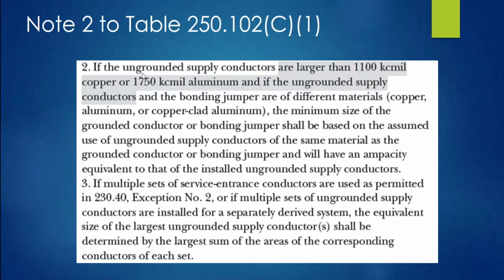Okay, again, if the ungrounded supply conductors are larger than 1100 and 1750, and if the ungrounded supply conductors and the bonding jumper are two different materials, in other words, the aluminum conductor's coming in and the bonding jumper is copper, the minimum size of the grounded conductor or the bonding jumper, now we're talking about how you size it, shall be based on the assumed use of ungrounded conductors of the same material as the bonding jumper, right? So again, aluminum conductors coming in, the bonding jumper is copper. You're going to size that copper bonding jumper. You're going to determine what size those conductors are that are coming in as if they were copper, just like the material for the bonding jumper, using the ampacity to size it.